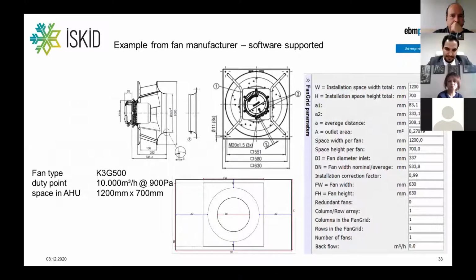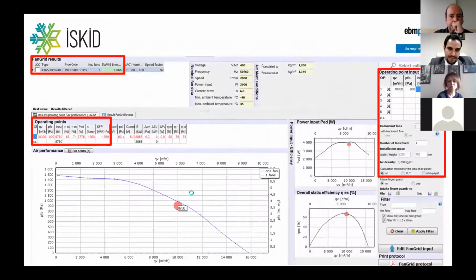So how is this in practical use? For example, in our fan software, we tested. We have a certain way of expressing the losses. So you can enter the width and the height of the unit, which results in the different data, average distance, and so on, the diameter of the fan and the nominal diameter, etc. And then this is calculated. You see here, for example, 10,000 cubic meters per hour against 900 pascals.